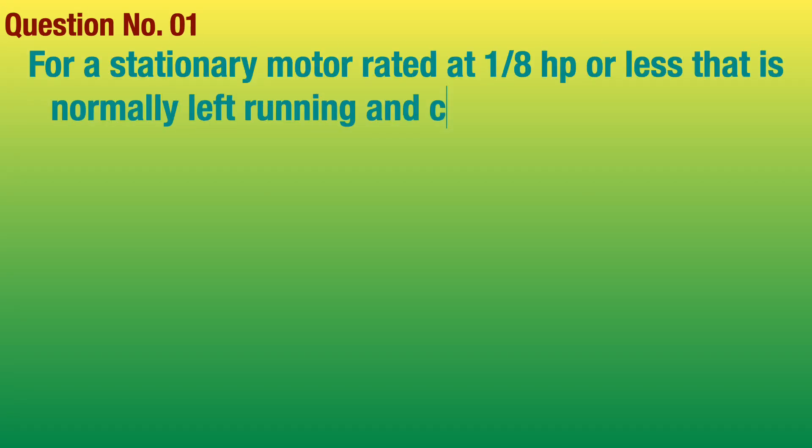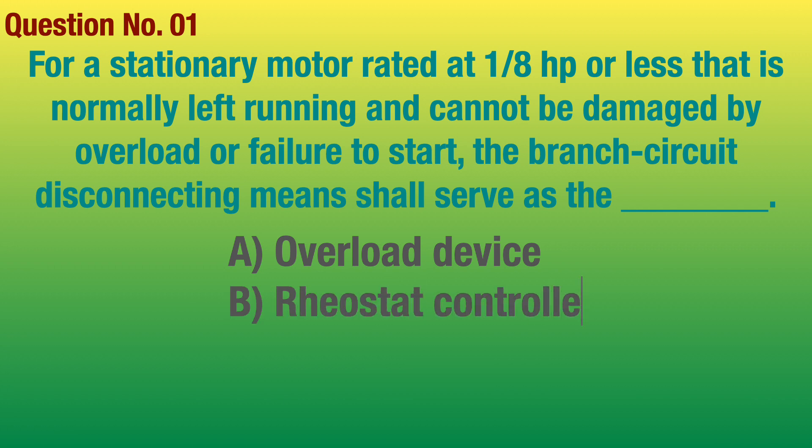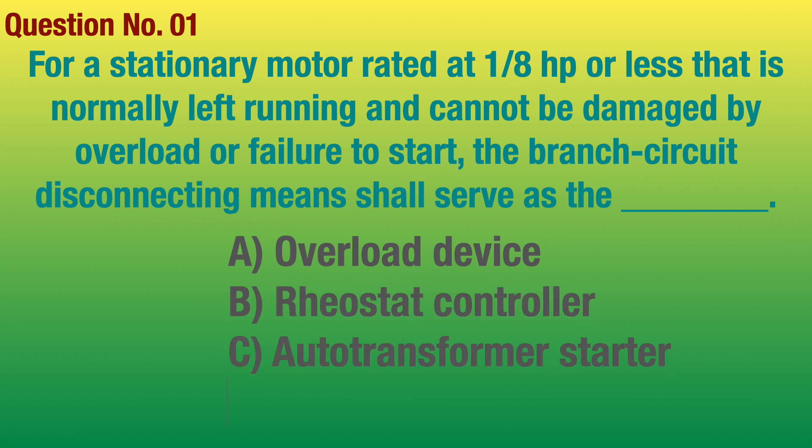Question number 1. For a stationary motor rated at 1/8 horsepower or less, that is normally left running and cannot be damaged by overload or failure to start, the branch circuit disconnecting means shall serve as the blank. Answer: Motor controller.